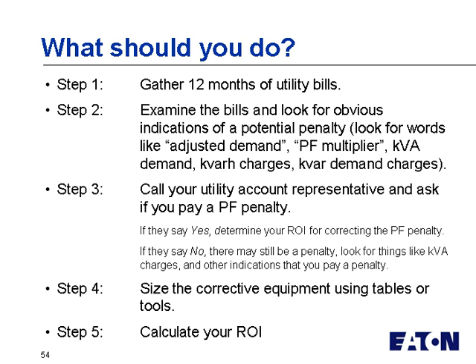The next step would then be to size the corrective equipment using tables or tools that we showed that are available. And again, power factor correction equipment manufacturers will have the tables and tools available to do that. And then you calculate the return on investment. And most people, I find, accept less than about a 2-year payback. And coincidentally, most of the applications that I've looked at are well less than 3 years, and most are less than 2 years. A lot are less than 1 year, so it's very, very appropriate to apply this equipment.